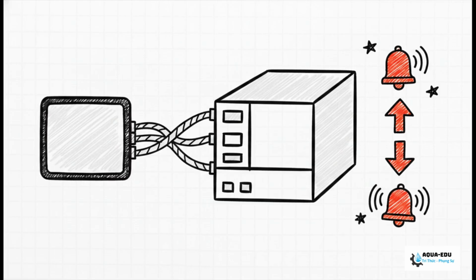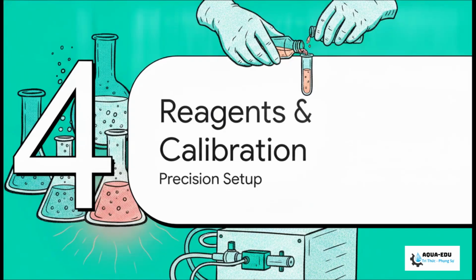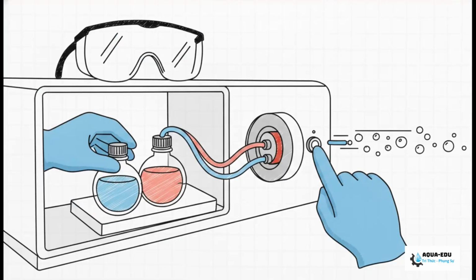And a low alarm at 0.05 milligrams per liter to ensure our primary disinfection hasn't actually failed upstream. All right, Section 4, Chemical Reagents and Calibration. Wearing your chemical-resistant gloves and safety goggles, open up that front compartment. Install the DPD reagent and buffer bottles firmly into their designated slots right on the white plastic tray. Carefully connect the color-coded Tygon tubing exactly as it's mapped out in the manual.